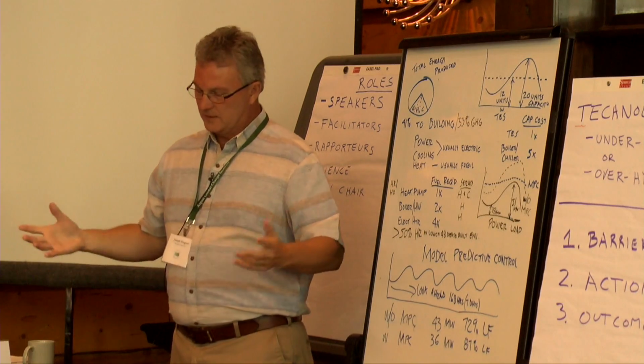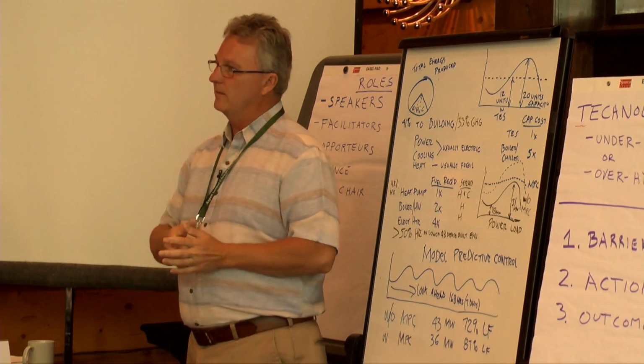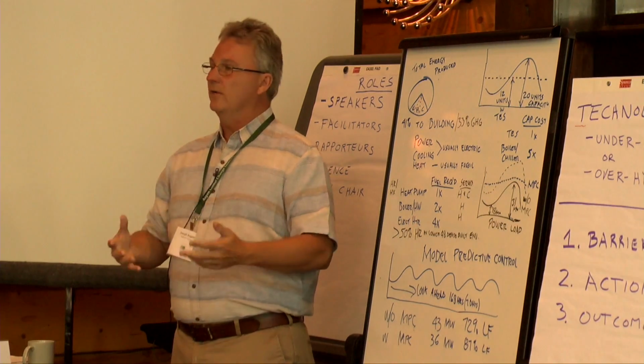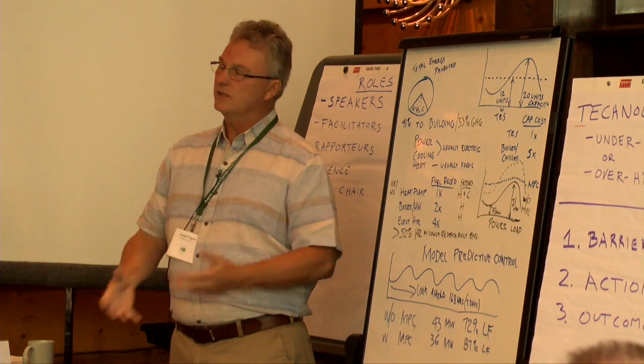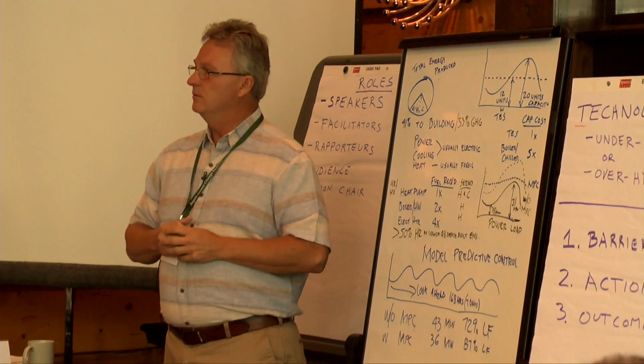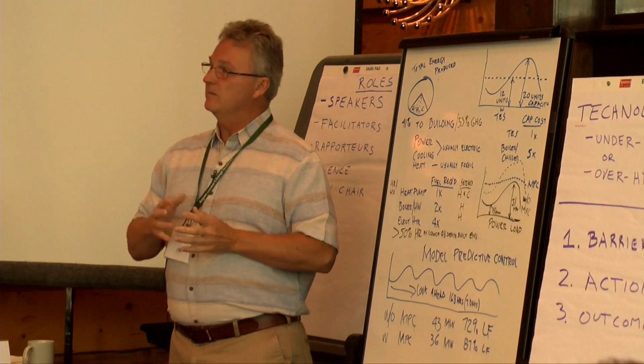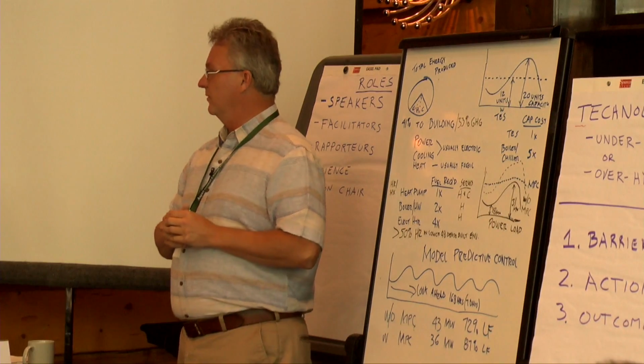So preferentially, if I was designing a system for a university anywhere in the United States, I would first use the recovered heat from my chilled water system on my campus, and second, augment it with ground or lake, river, or ocean source heat exchange using the heat pump to extract heat from those places to provide the remaining heat I can't get from heat recovery. You do all that and you have a fully electrified system that you can move. So maybe that's the 80% conversion, or maybe this is part of the 20%, but that's the long-term strategy if you don't want to do carbon capture and storage of burning fossil fuel on your campus or your city or wherever, or if you don't want to try and go the sustainable biofuels route.